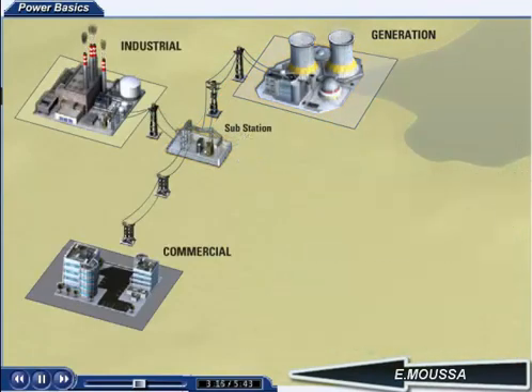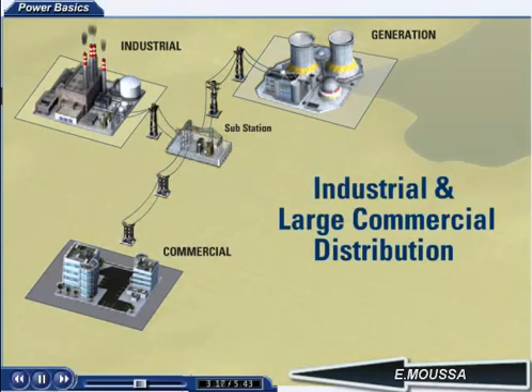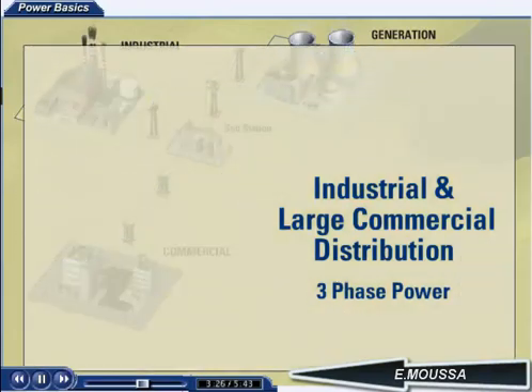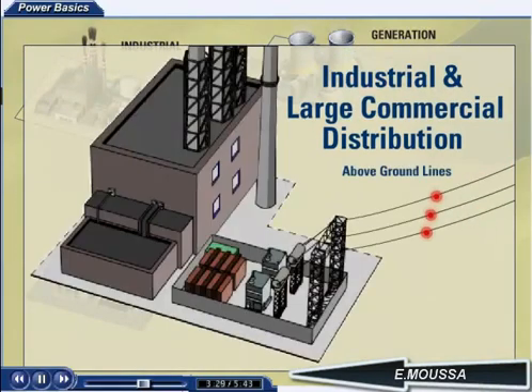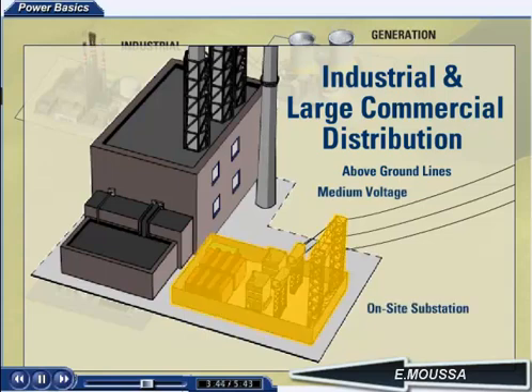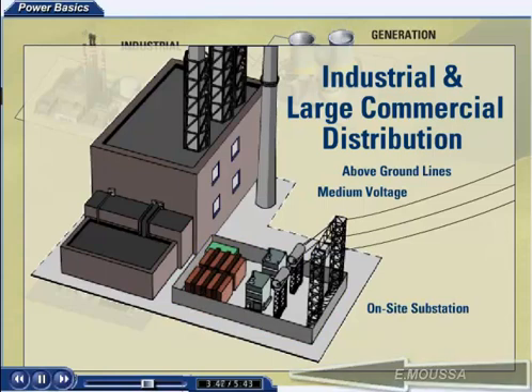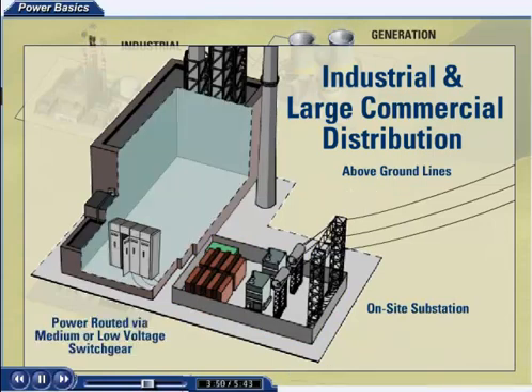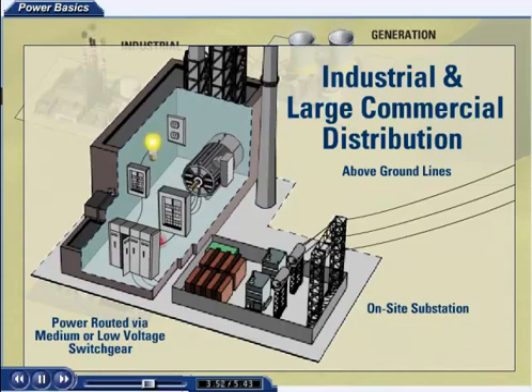The distribution system for a typical industrial or commercial user shares some similarities to that of the residential customer, with the major exception that the power being delivered is usually three-phase. From the substation, the industrial or commercial power lines take the power above or below ground to a large transformer, which steps the three-phase voltage down to a suitable level for the plant or building. For larger commercial or industrial users, this voltage may be in the medium voltage range. In this case, there will be an additional substation on site. The power would then be routed from the transformer or transformers via medium or low voltage switchgear to different areas of the plant or building for further distribution via switchboards and panel boards.